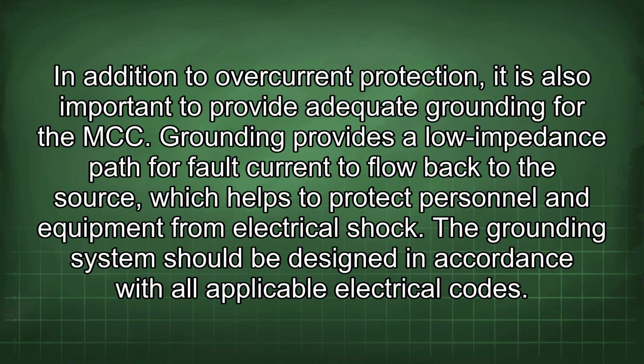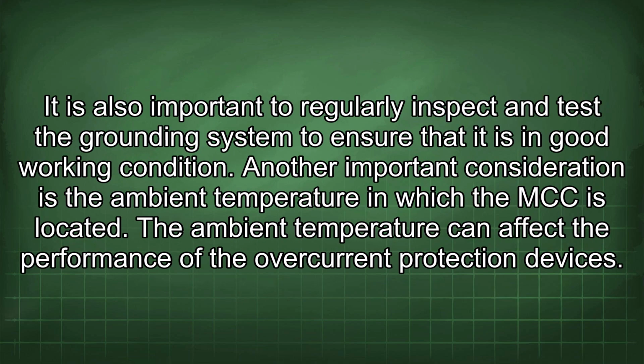In addition to overcurrent protection, it is also important to provide adequate grounding for the MCC. Grounding provides a low impedance path for fault current to flow back to the source, which helps to protect personnel and equipment from electrical shock. The grounding system should be designed in accordance with all applicable electrical codes. It is also important to regularly inspect and test the grounding system to ensure that it is in good working condition.